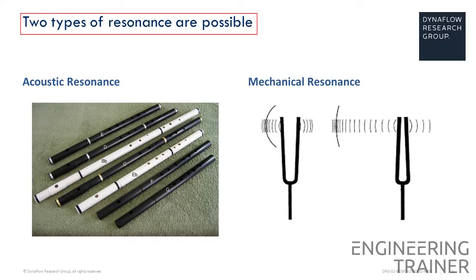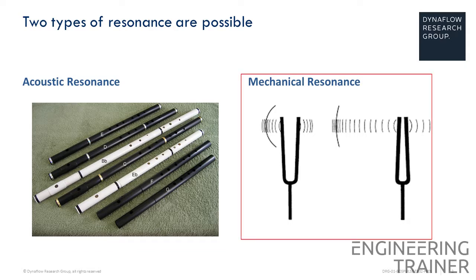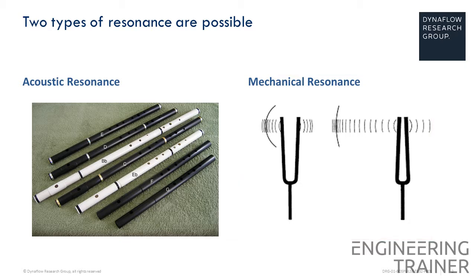Two types of resonance are possible in the context of pulsations. The first is acoustic resonance, which is the amplification of pressure variations in pipes and influences the magnitude of the pressure pulsations themselves. Secondly, there is mechanical resonance, which influences the magnitude of the vibrations, so the displacements of the object. We need to take into account both acoustic and mechanical resonance as they both impact potential vibrations in piping and the resulting fluctuating material stresses.